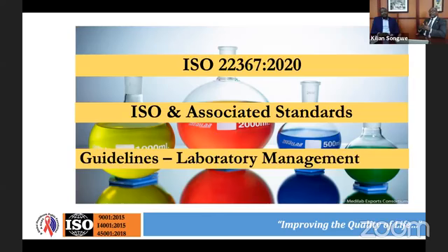Because when you get a result, let's say you had a quantitative result, the fact that you had a hemoglobin of 12.3 does not suddenly mean that it's acceptable if there wasn't a predefined criteria that was actually agreed to before you did the interlaboratory comparison. So when we talk about interlaboratory comparison, it is key that our laboratories actually understand the requirements before you get engaged in interlaboratory comparison. It's not just about looking at what is the value of the result when you have it.